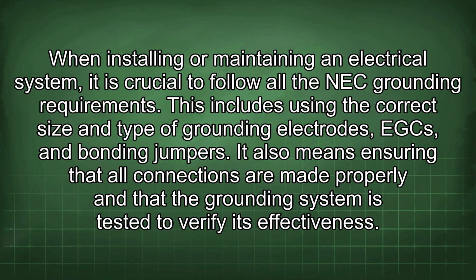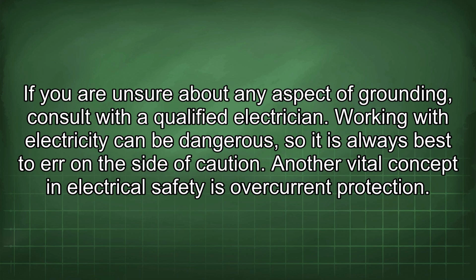When installing or maintaining an electrical system, it is crucial to follow all the NEC grounding requirements. This includes using the correct size and type of grounding electrodes, EGCs, and bonding jumpers. It also means ensuring that all connections are made properly and that the grounding system is tested to verify its effectiveness. If you are unsure about any aspect of grounding, consult with a qualified electrician. Working with electricity can be dangerous, so it is always best to err on the side of caution.